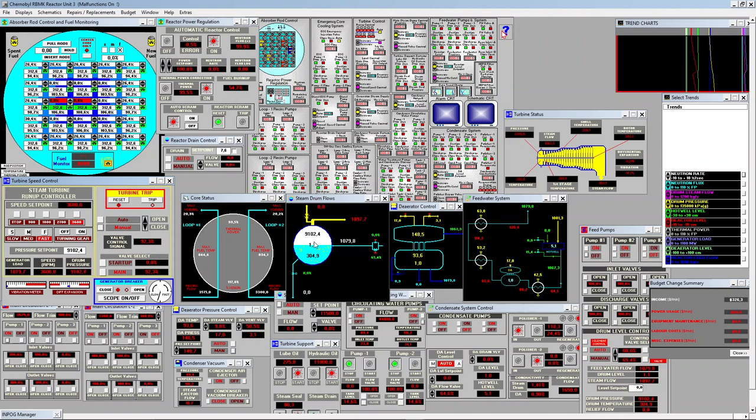The second one, with too low pressure, basically the reactor system will work out of specs, because this is a boiling reactor. Well, not exactly, it's an RBMK, but basically water boils within the drum and within the reactor core. So if you decrease the pressure, you will have more boiling, more voiding, which is the ratio of steam within the reactor water, which changes the neutronic parameters and reactivity of the nuclear reaction.